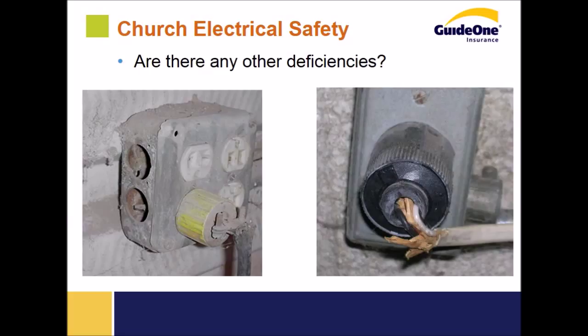Do you note any other deficiencies? Here's just some examples of damaged and inadequate cord ends. We've got insulation that's frayed and worn, knockout covers removed, and dirty and dusty conditions. All of this can lead to problems. In the image on the right, you can see even the thin wall conduit has been separated from the connector—that's another concern. So as minor as these conditions may seem, we need them reported, we need pictures of them, and we need appropriate recommendations made.